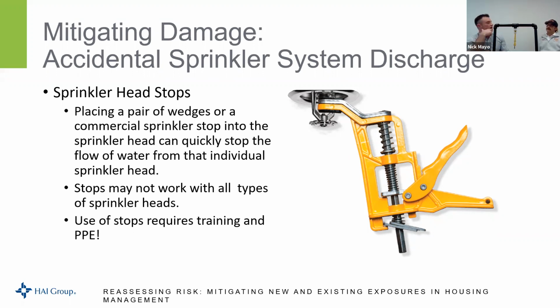Or 9 times out of 10, what we do is we take off our helmet and put it over the sprinkler head until we can find an isolation valve, because we just can't see anything that's going on once the sprinkler head is activated. So devices are available. They're simple to install when water is not flowing, but when water is flowing out of them, it does get a little complicated, and that's why training, experience, knowledge, and personal protective equipment is important.